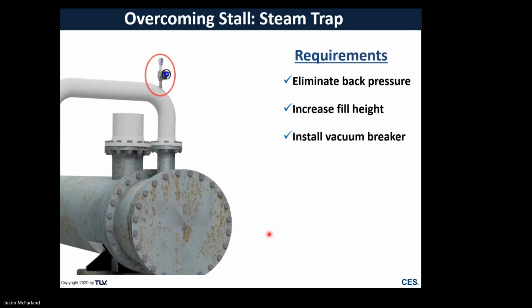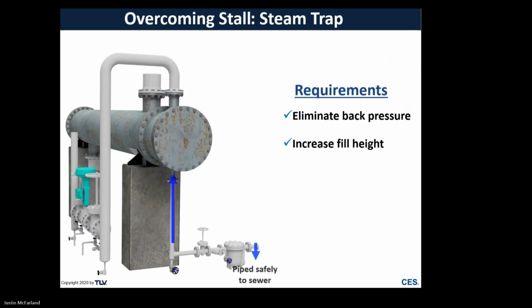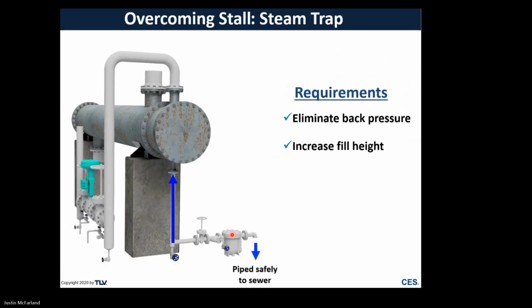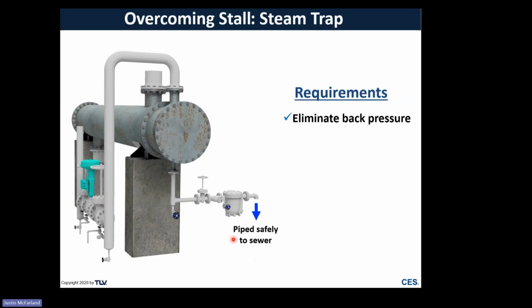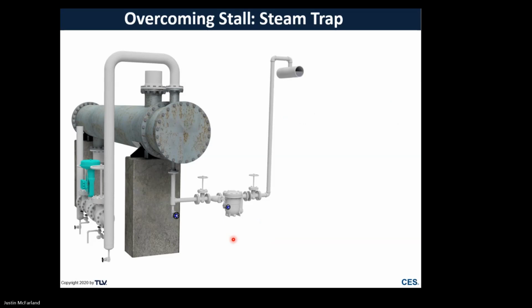Justin, can you speak to why you can't lift the trap up to decrease your back pressure? Lift the trap up like this? Like if you had the header up above and you raised the trap up to the header height. What problem would that cause? I'm kind of leading you, but what problem does that cause?